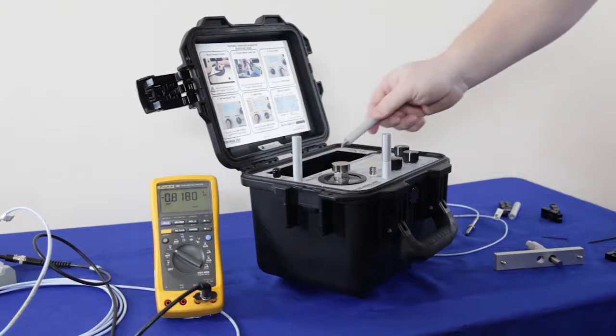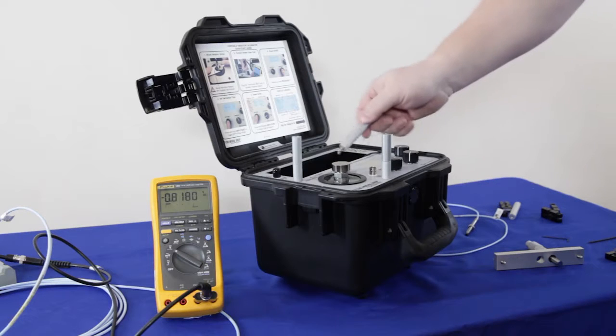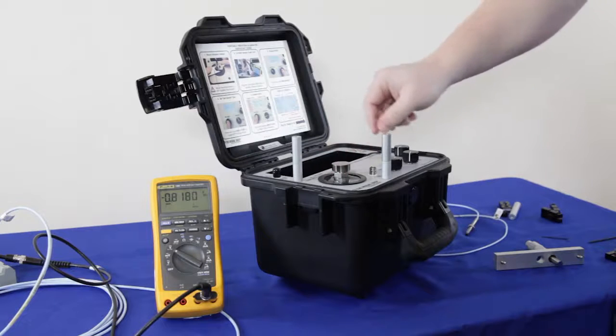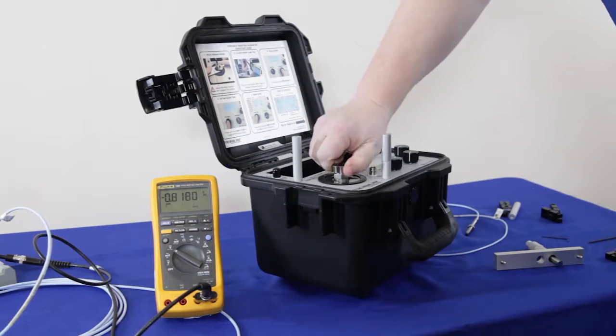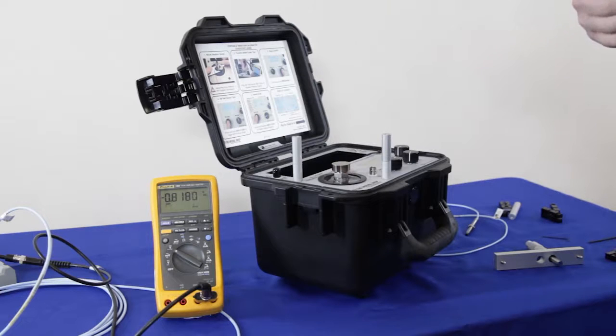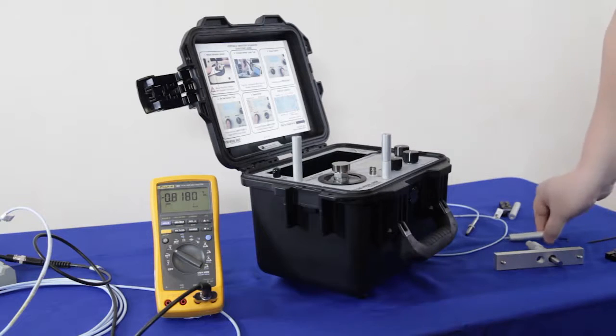The other thing you can't forget is to make sure you have the 4140 steel target mounted on top of the shaker, and you don't have to tighten that up with any sort of wrench or anything. Just hand tight is fine because torque is not critical in this application.